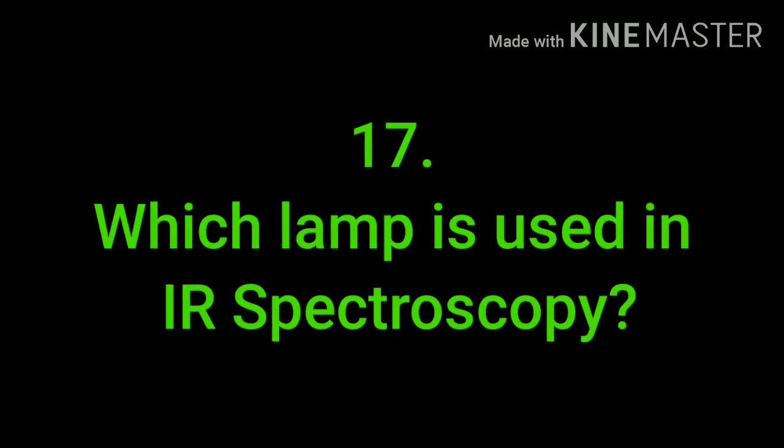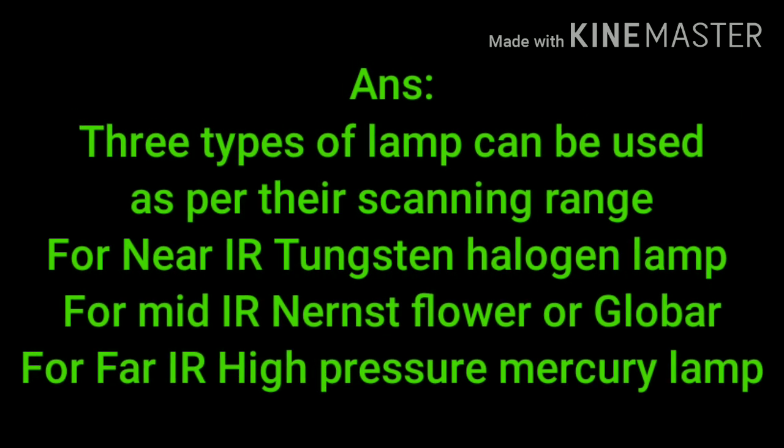Which lamp is used in IR spectroscopy? There are three types of lamps used. For near IR, a tungsten-halogen lamp is used. For mid IR, a Nernst filament or Globar is used. For far IR, a high-pressure mercury lamp is used.